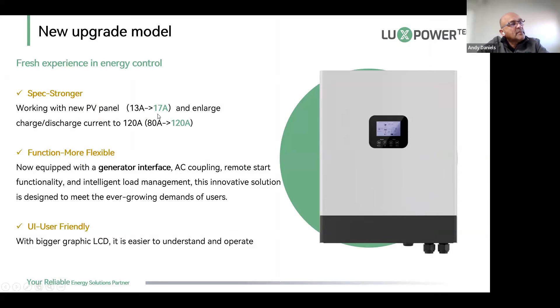The spec is stronger — we now have a new working mode with PV panels running up to 17 amps. We've also enlarged the discharge and charge current: on the old LXP5 we were limited to 66 amps, then upgraded to 80, but now with the new machine we can charge and discharge at 120 amps DC. The function mode is more flexible, and the machine is now equipped with a unique generator interface.